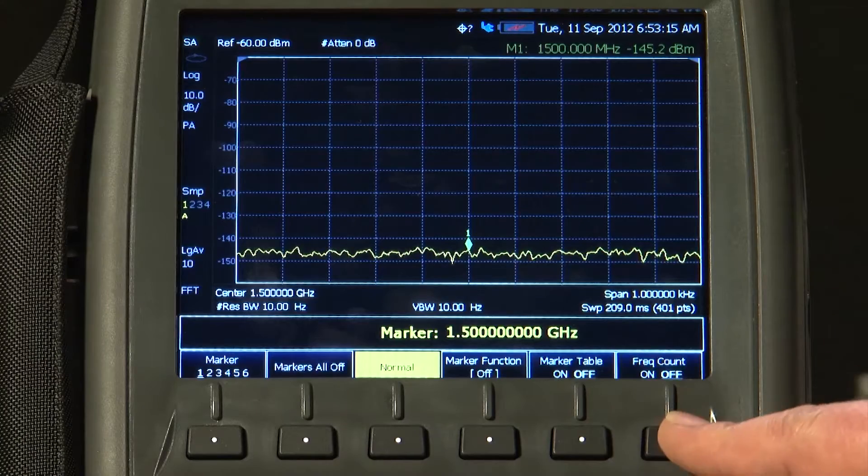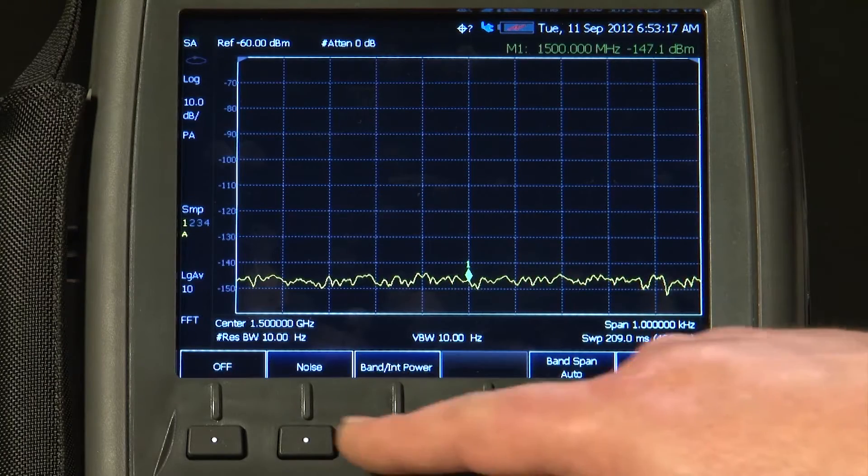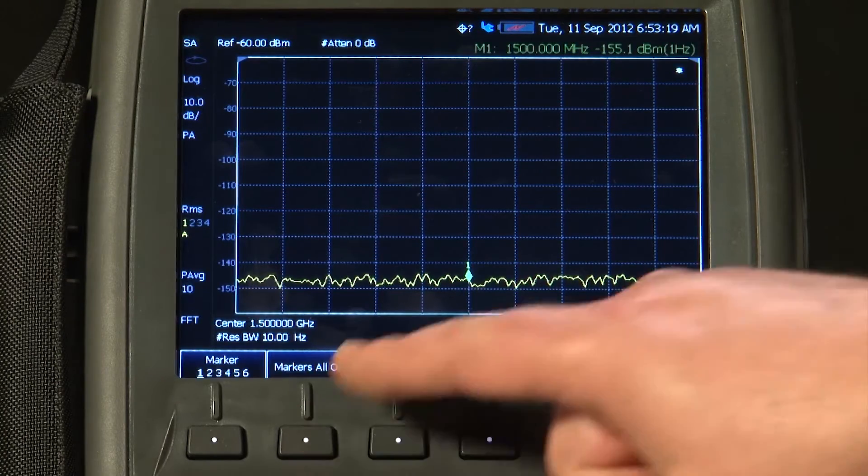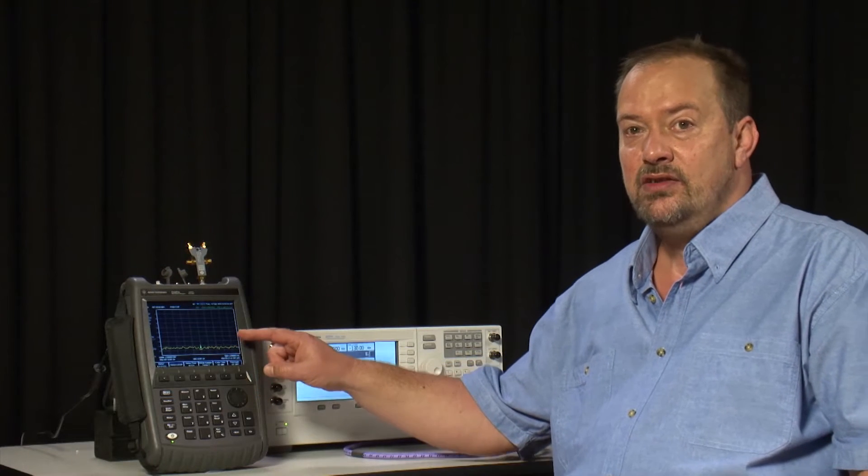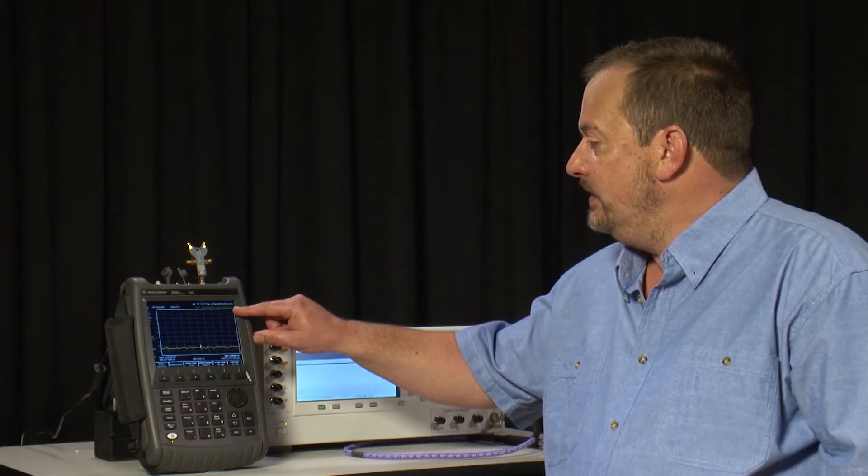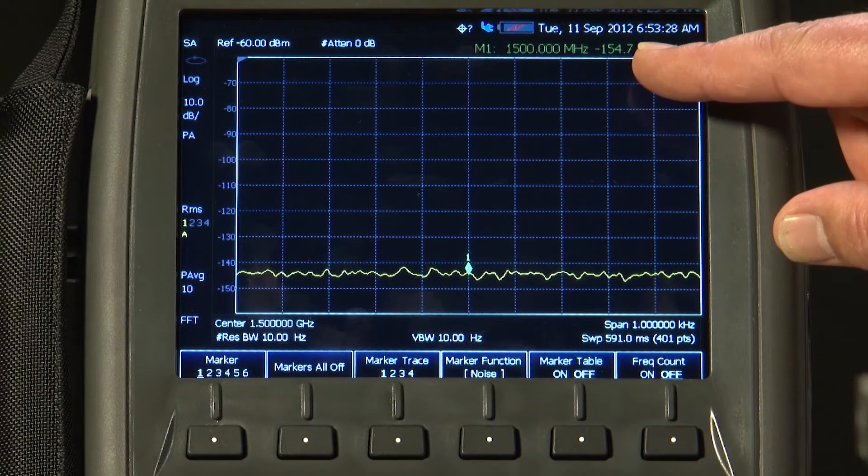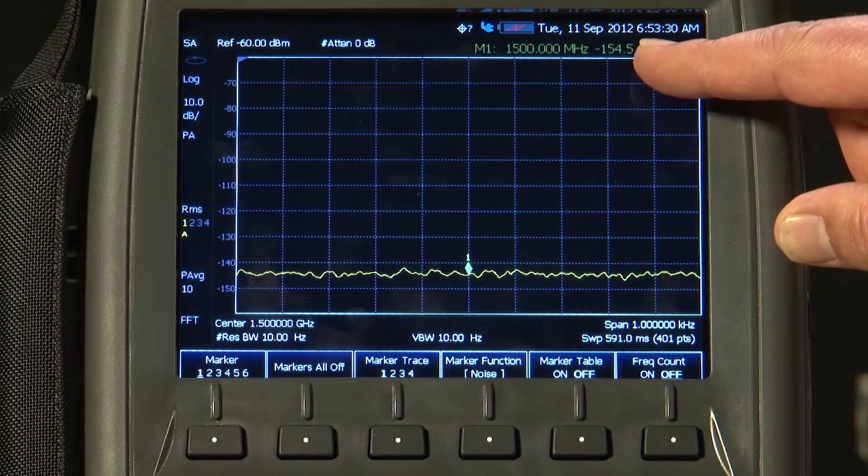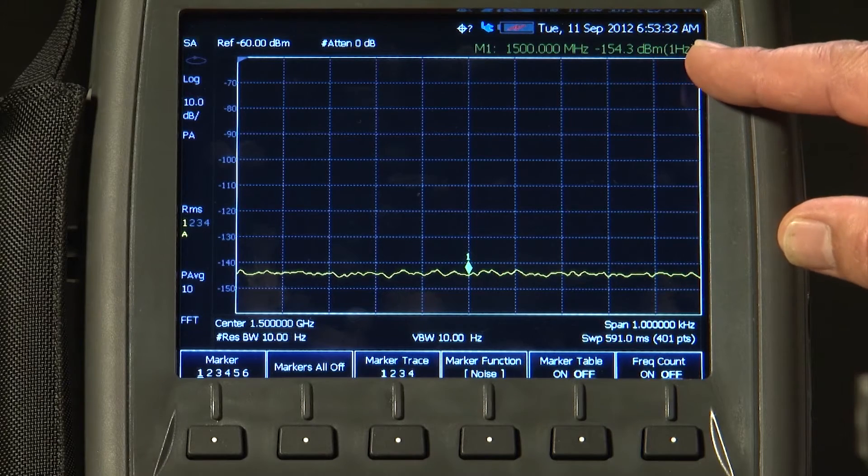If I press more marker function and the noise marker, this will normalize the amplitude measurement to make it as if we were measuring within a 1 Hz bandwidth. You can see here that we have a noise floor, or displayed average noise level, of about minus 154.7 dBm per Hz.